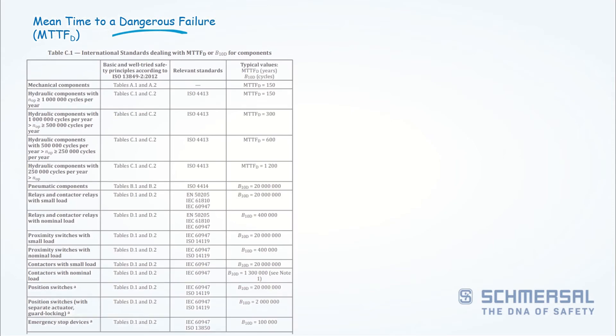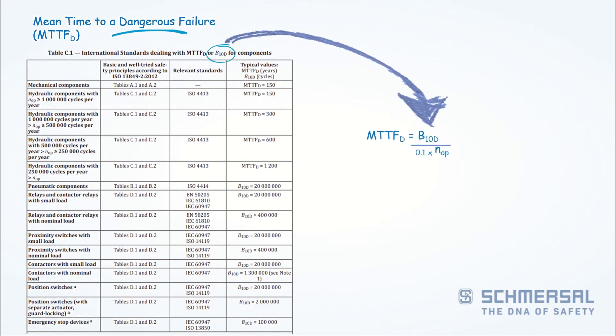It also looks at the mean time to a dangerous failure, which is the wear and tear on electrical and mechanical components. Here we have to do some calculations. We have to obtain the B10D value from the manufacturer or from the table in the standard, and do a quick calculation because we have to determine how often we are relying on the safety function to activate — so we have to calculate the wear and tear.